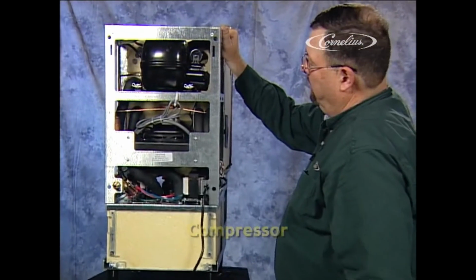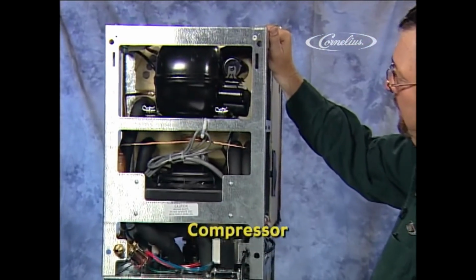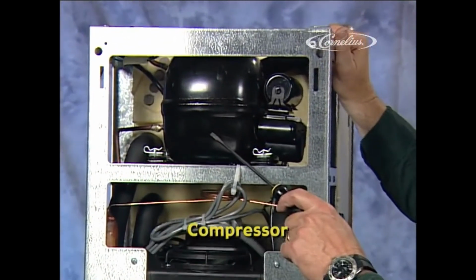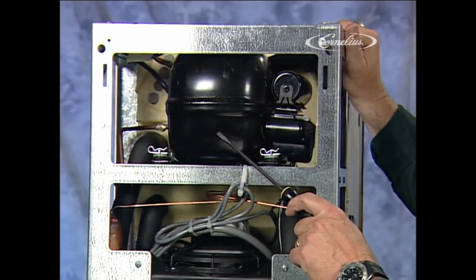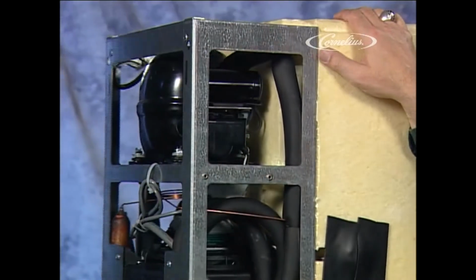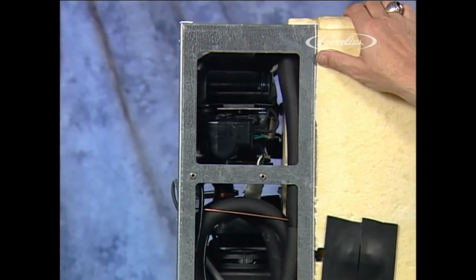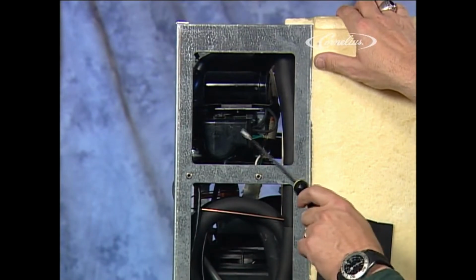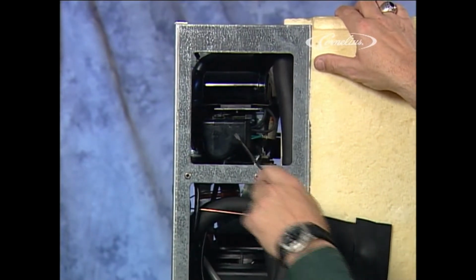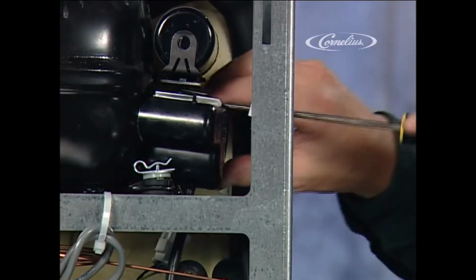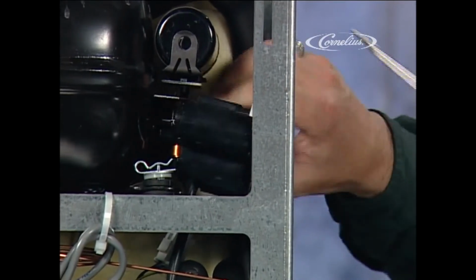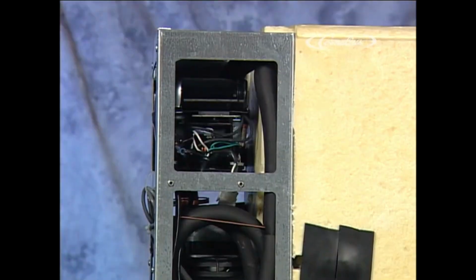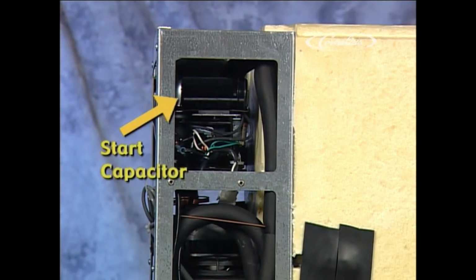The compressor is a 1/10 horsepower capacitor start induction run motor. It has 2 sets of winding, start and run. To properly understand how it works, we need to first examine the electronic components. They are located under this cover. To remove, insert a screwdriver in the slot and gently press down while at the same time pulling the cover back. In this application, the capacitor is used for startup only.